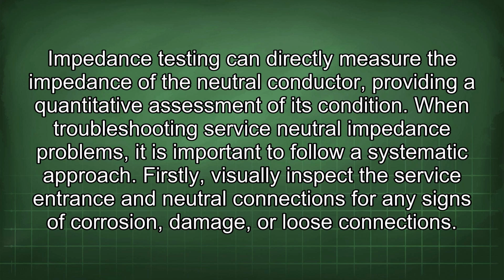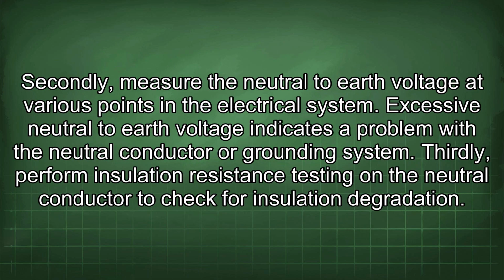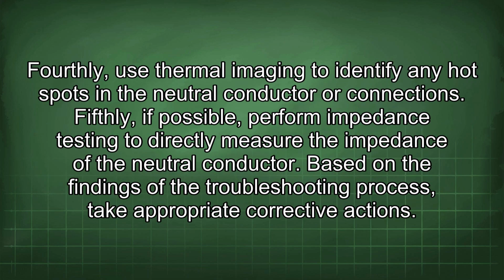Firstly, visually inspect the service entrance and neutral connections for any signs of corrosion, damage, or loose connections. Secondly, measure the neutral to earth voltage at various points in the electrical system. Excessive neutral to earth voltage indicates a problem with the neutral conductor or grounding system. Thirdly, perform insulation resistance testing on the neutral conductor to check for insulation degradation. Fourthly, use thermal imaging to identify any hot spots in the neutral conductor or connections. Fifthly, if possible, perform impedance testing to directly measure the impedance of the neutral conductor.